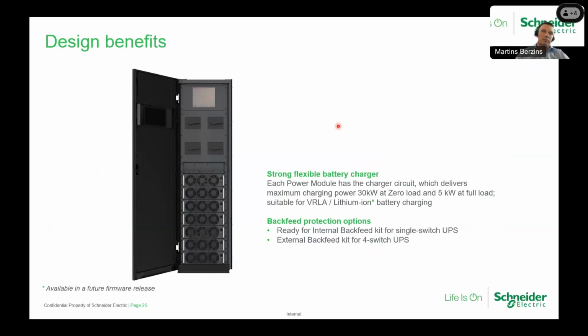So some additional design benefits for particular models. Each power module has a charger circuit inside, which can deliver a maximum of 30 kilowatts at zero load and 5 kilowatts of charging power once it's fully loaded. And the UPS can accept VRLA or valve-regulated lead-acid batteries and lithium-ion battery configurations. We also have a backfeed protection option. For a single switch UPS, we have a kit ready as an internal backfeed kit. But for the 4-switch model, an external backfeed kit is necessary if such is the requirement.